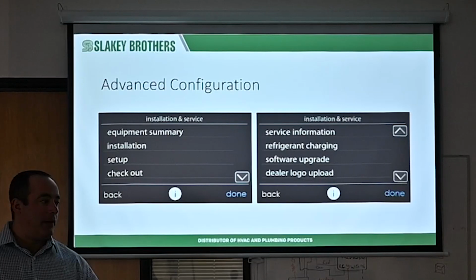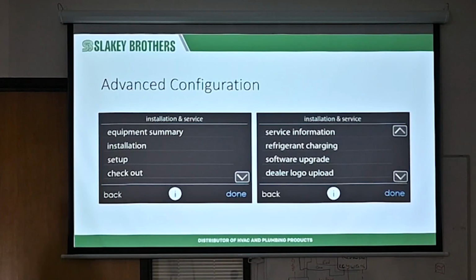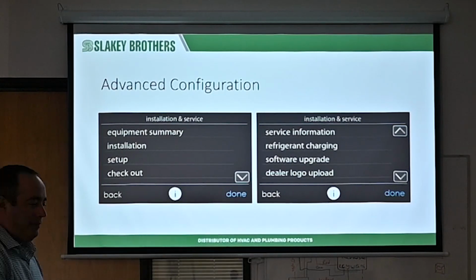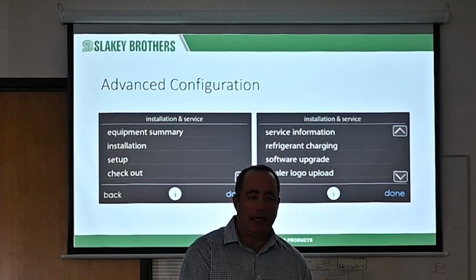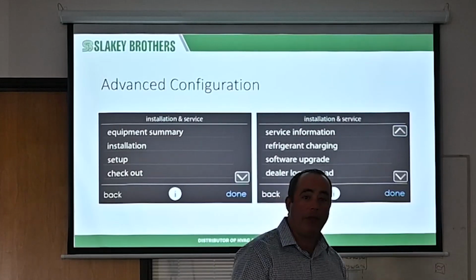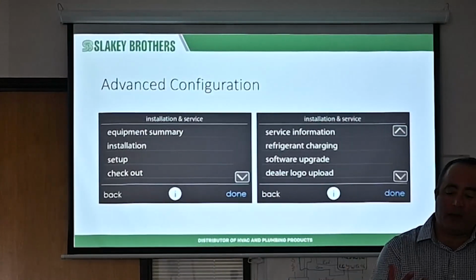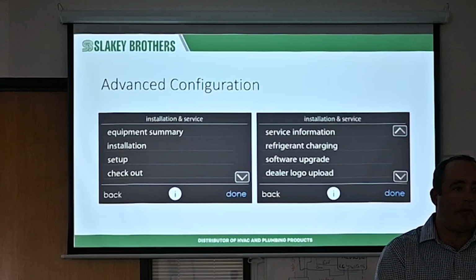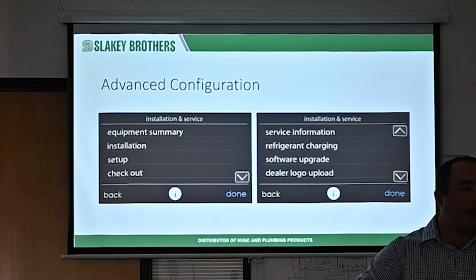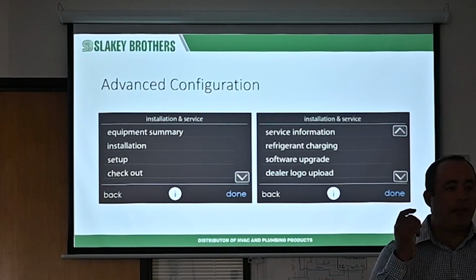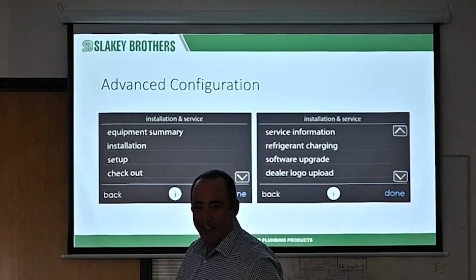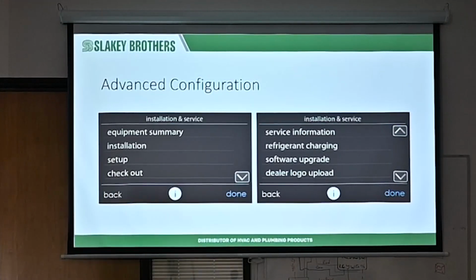That way, you know, Alan goes up to the job site and the Evolution Extreme, I love it. I can leave all my tools in the truck, walk up to it, click, wait, and then I'm already checking my subcool, my superheat, my voltage. I pretty much checked it all out. There's my maintenance. I take a screenshot, one page, screenshot, second page, then I turn it off, rinse it off, whatever, turn it back on, and my maintenance is done. Or update the software, or I can find out what's wrong with the unit if it's not working.